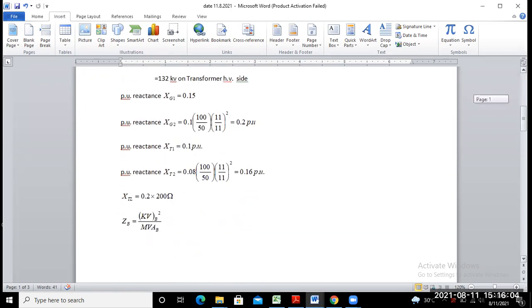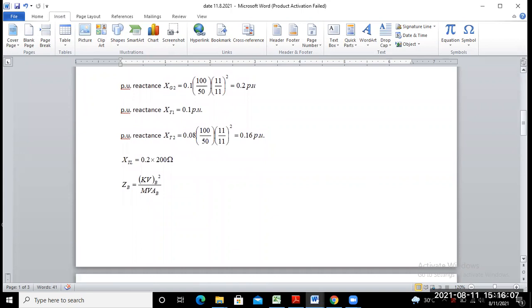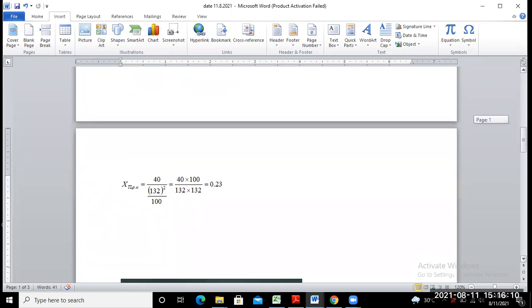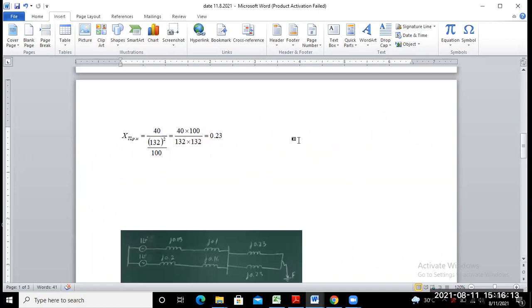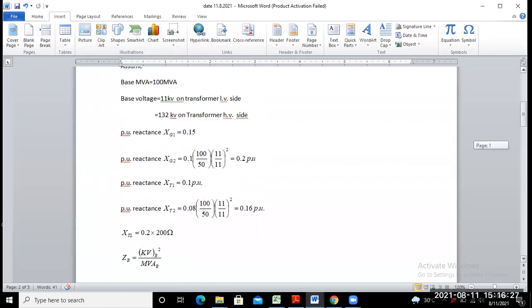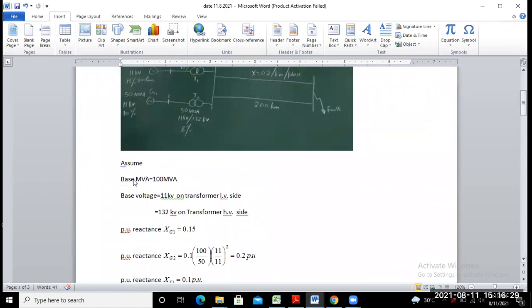So, up to this point, I think we already found the per unit reactance value on the common base MVA and base voltage. Whatever components are involved in our power system, all are converted to per unit values on the common base MVA and base voltage, that is generator 1, generator 2, transformer 1, transformer 2, and transmission line.